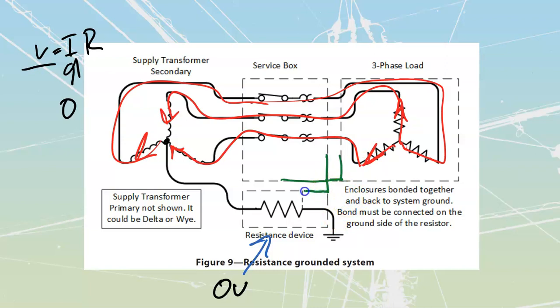But then we're going to connect on the ground side of the resistor. This is so critical that the bond has to be connected on the ground side of the resistor. If you connect it over here instead, you've completely defeated the whole way the system is going to work—we'll cover that in a second. It has to be connected here, and then this conductor from the neutral grounding device goes back up and has to be an insulated conductor. It needs to be insulated as white or gray, and insulated to the same value as my phase, because we're going to drop phase value of resistance across here.